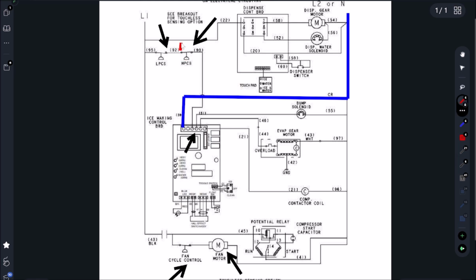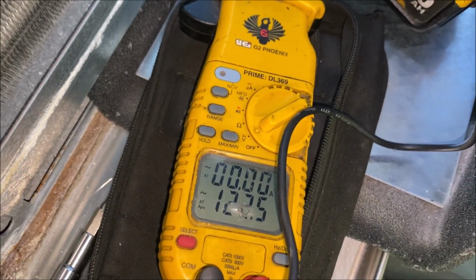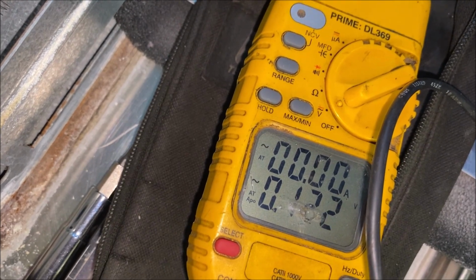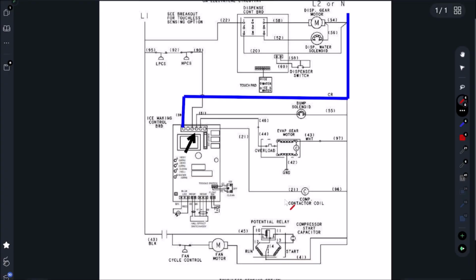I'm going to put a jumper right here just for testing purposes. We're going to jump out this switch. All right, so let's go ahead and jumper out this high pressure cutout switch, the 2 purple wires. And now we're going to test our fan cycle switch. We have 120 volts into the switch, 0 volts potential difference across the fan cycle switch.